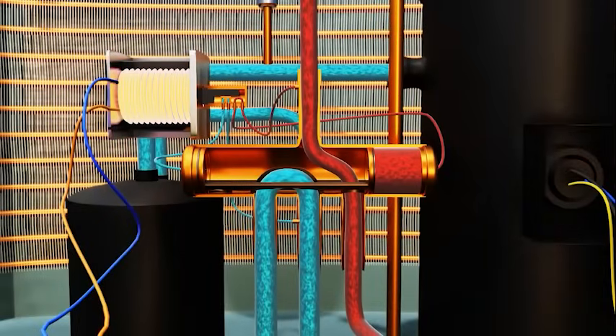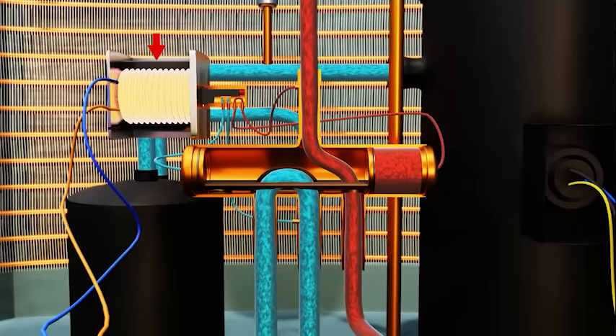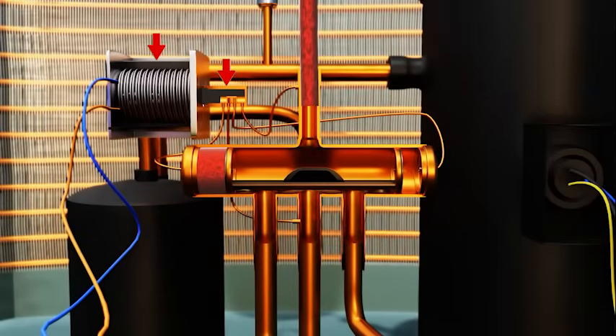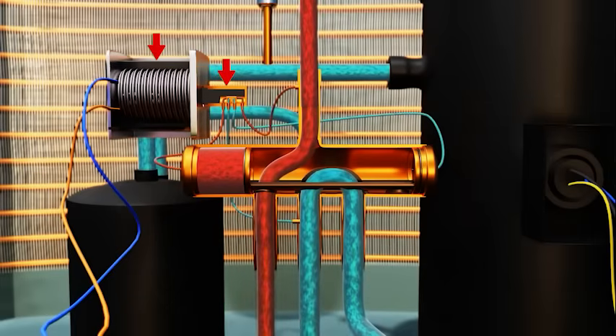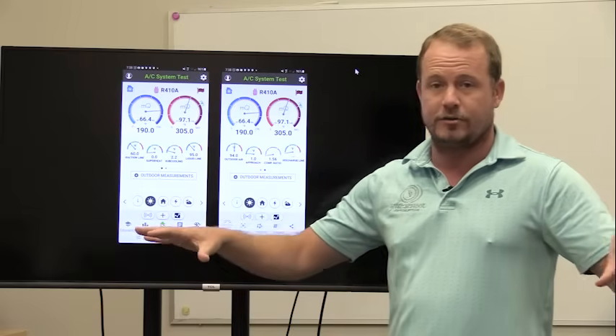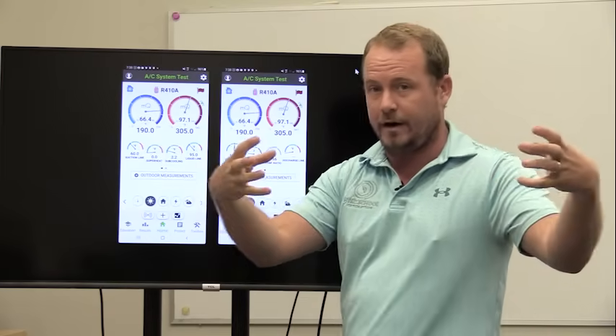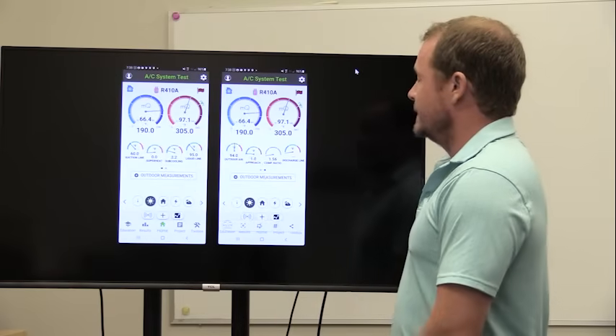Just keep in mind with the reversing valve, it's not that magnetic solenoid that actually shifts the valve. That magnetic solenoid shifts the pilot valve, which is kind of like a small reversing valve inside the reversing valve. And then those pressures from the compressor, those differential pressures are what actually shift the valve. And that's why you can't shift a reversing valve when the system's off. The system pressures are equalized at the same level, that valve's not going to shift because it requires that discharge and suction to slide the valve.